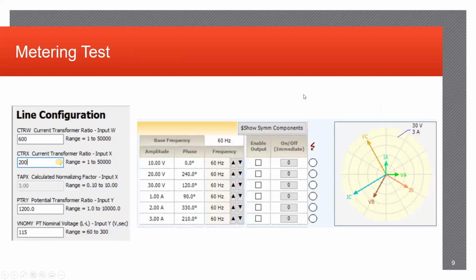So the first test you always want to run after you've taken all your necessary recorded data, such as the SER event recordings, history of the relay, stuff like that. The first thing you want to do when initially setting up your test is a metering test. This is extremely important because you want to correctly identify that the voltage and current values that you are injecting correctly replicate not only the relay settings ratios, but as well as the ratios that are identified on the field equipment.